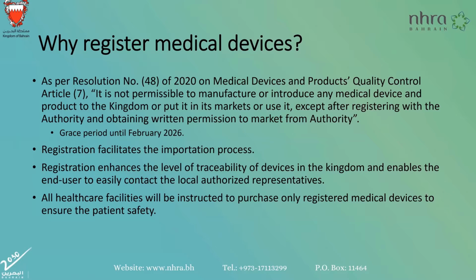However, since only a small percentage of the medical devices in Bahrain are registered at the moment, and in order to give the authorized representatives time to register their devices, this was not implemented directly, and a circular was circulated that it is mandatory to register all medical devices within the coming 5 years, meaning that from February 2026, no medical device will be allowed to enter Bahrain market if it's not registered in NHRA.